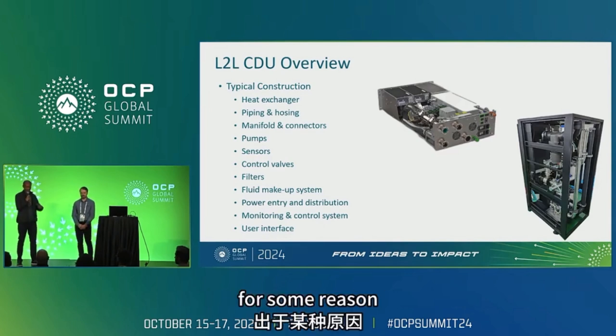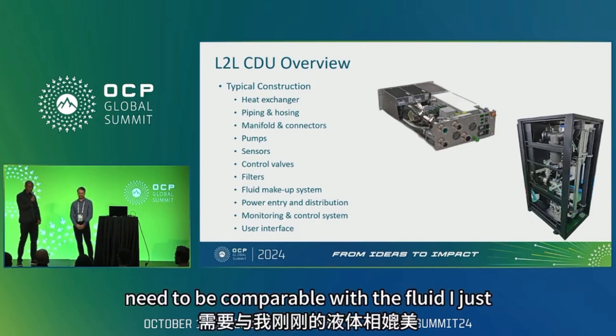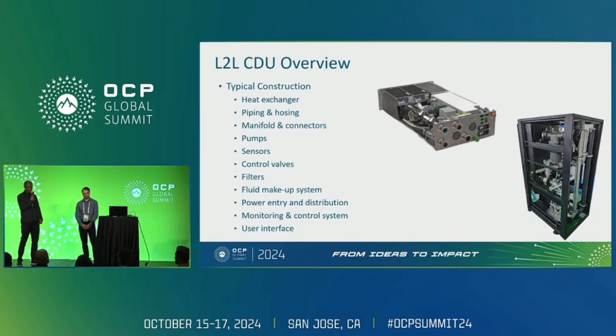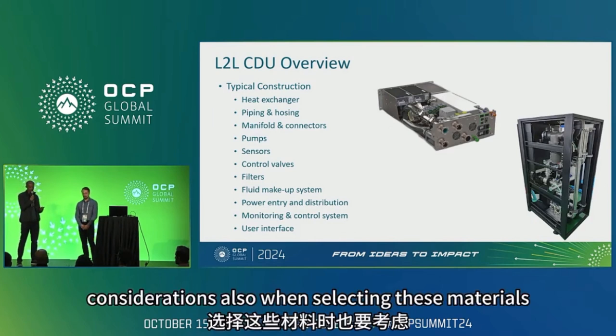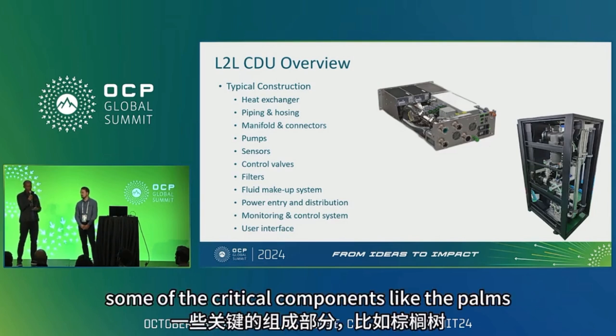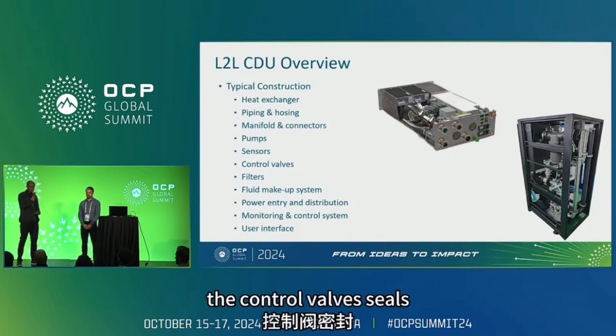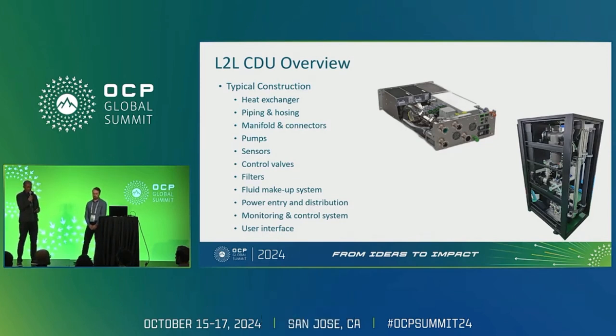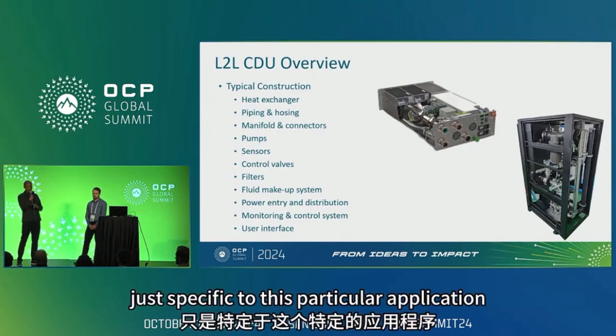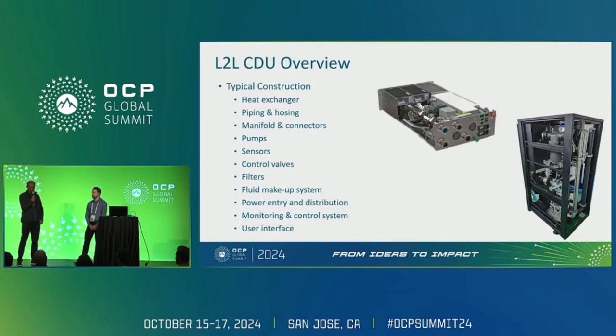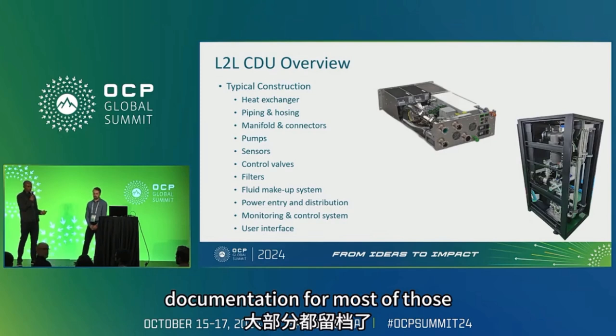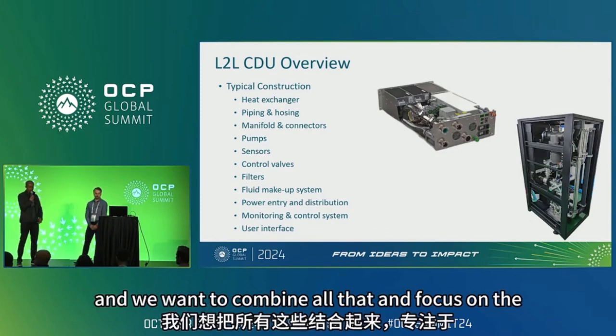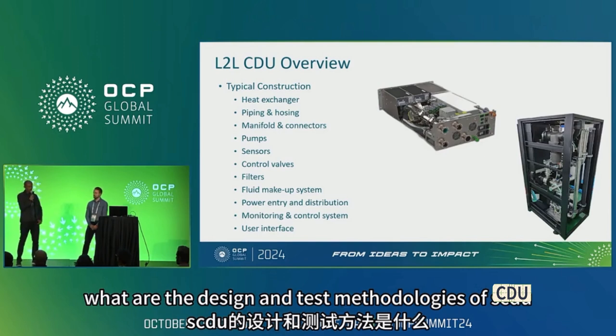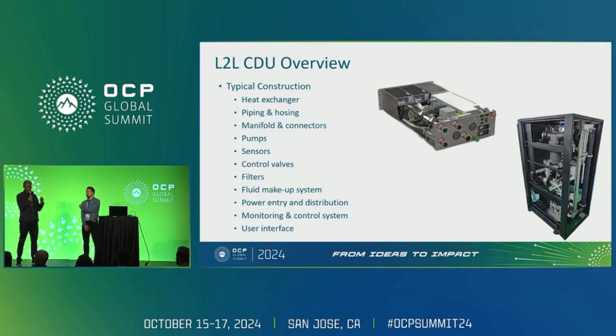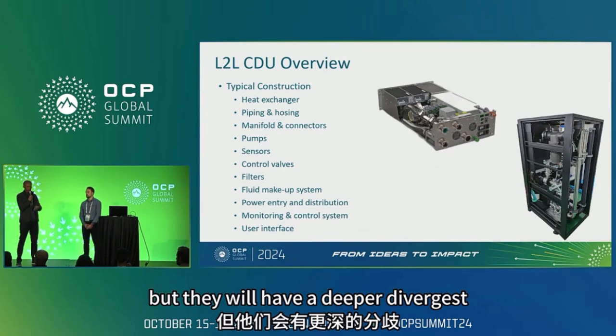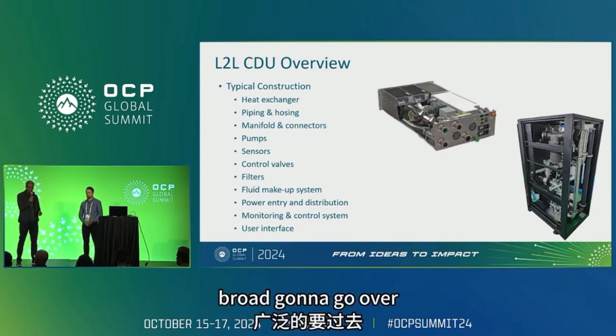All the ingredients going into that CDU need to be compatible with the fluid, as has been discussed, and other considerations also when we're selecting these materials, not just materials, even some of the critical components like the pumps, the filtration systems, the control valves, seals, just specific to this particular application, some of the areas need to be considered. There are documentation for most of those, and we're going to combine all that and focus on what are the design and test methodologies of a CDU. Details of this is in the document, but we'll have a deeper dive just in focus of the test methodology, which Brad is going to go over.